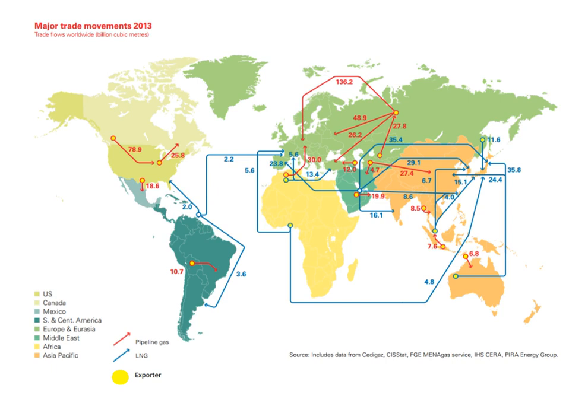Quantities of natural gas are measured in normal cubic metres (at normal temperature of 0°C/32°F and pressure of 101.325 kPa) or standard cubic feet (at 60°F/15.6°C and 14.73 psi). The gross heat of combustion of commercial quality natural gas is around 39 megajoules per cubic metre, approximately 49 megajoules per kilogram, assuming a density of 0.8 kilograms per cubic metre.